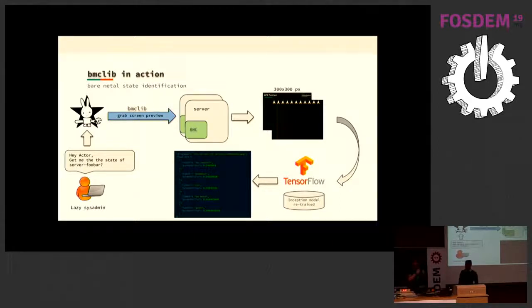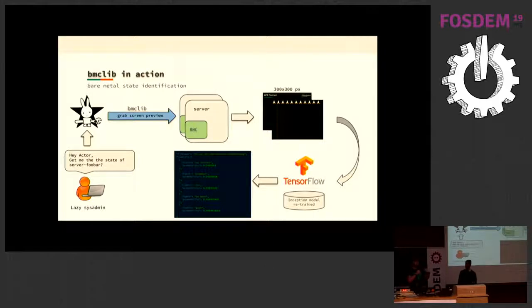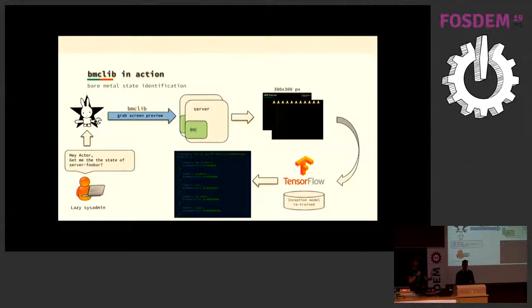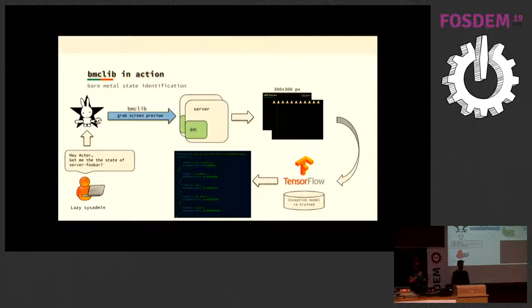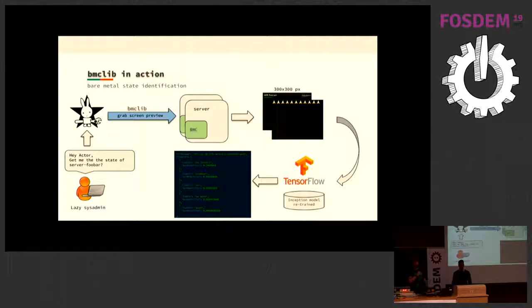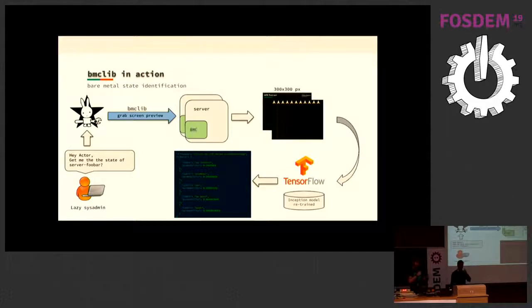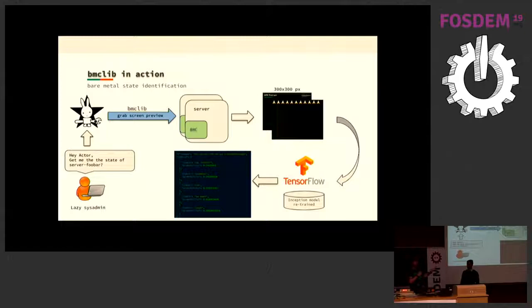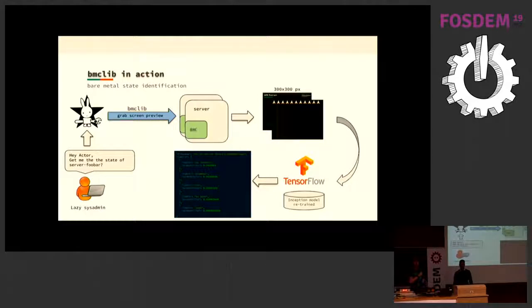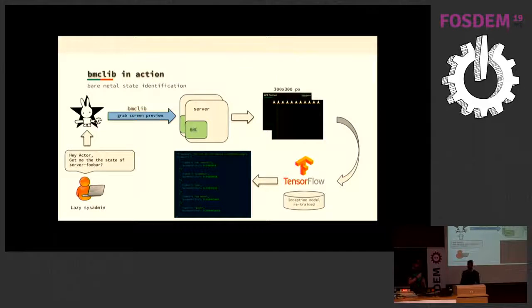A good example of that. We deal with a bunch of servers. Just to log in to the BMC and to troubleshoot what happens, it takes from six to eight minutes. Because you need to log in, you need to download the Java thing, you will need to open and check. And this can show in about five seconds if our issue is because someone actually didn't plug the machine properly inside of the data center. The way that we cable things, we always know that the out-of-band will work, but data might not be connected properly. And with the OCR, it will tell exactly that there is no media detected. So we know already that someone needs to go and check the physical connection.